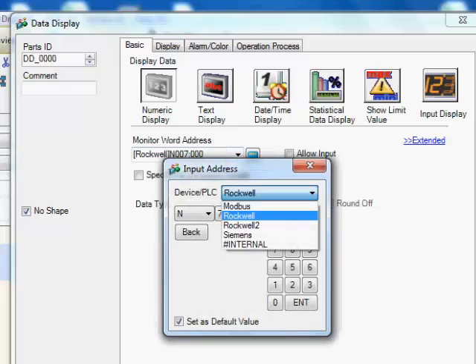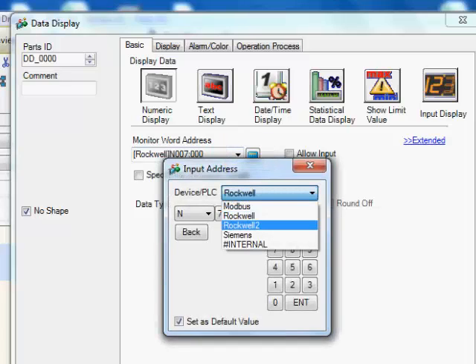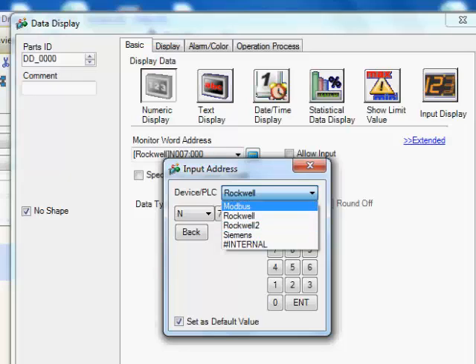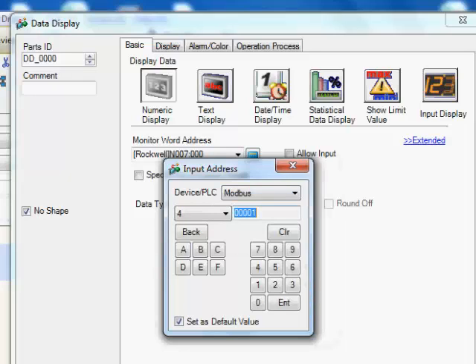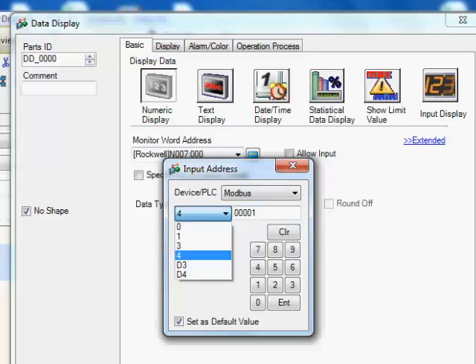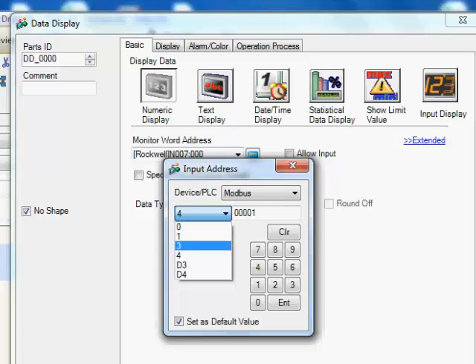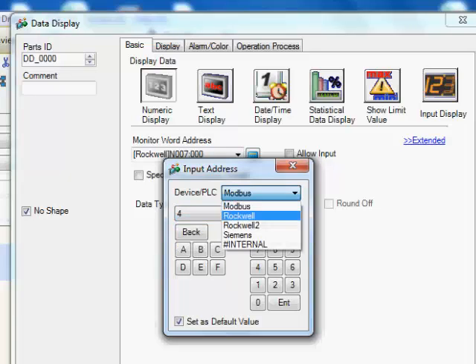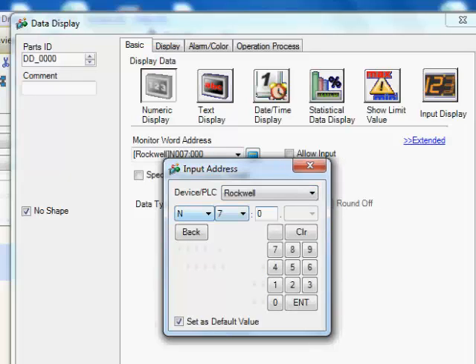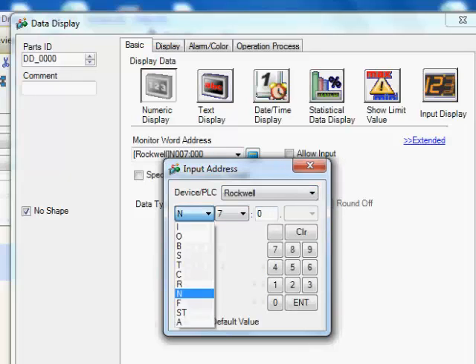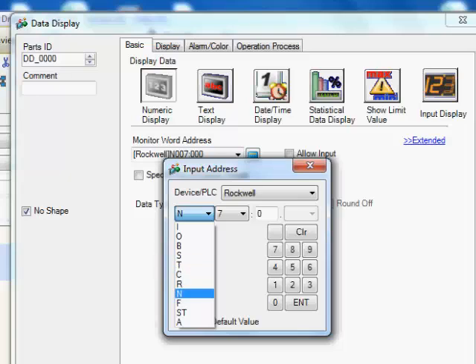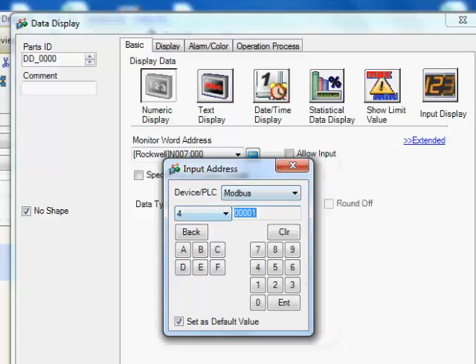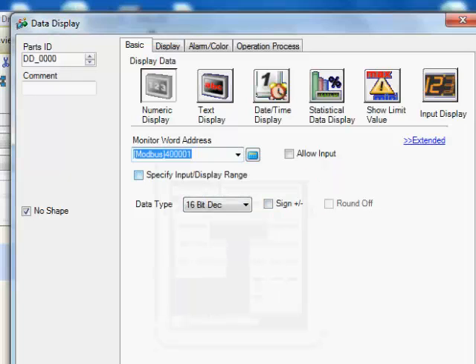What we do is actually parse each one so you can see all the names that we just created: Modbus, Rockwell, Rockwell 2 and Siemens. I'll select the Modbus, you get addresses like 40000 zeros, ones and threes, that's Modbus type addressing. If we were to select Rockwell you would see Rockwell type addresses, inputs, outputs, integers, things like that. We'll go ahead and do a Modbus one first and just do a simple 40001.